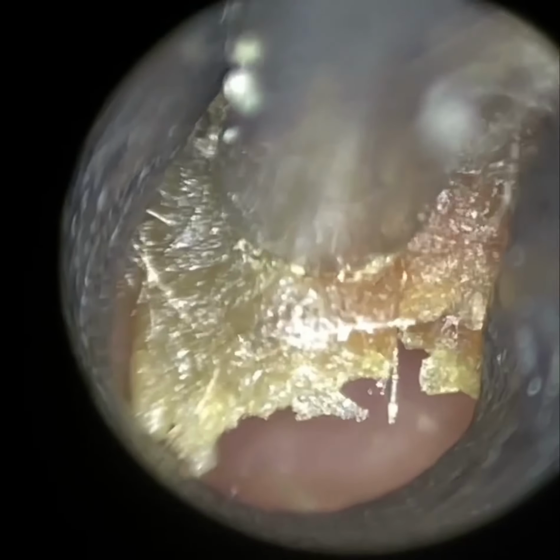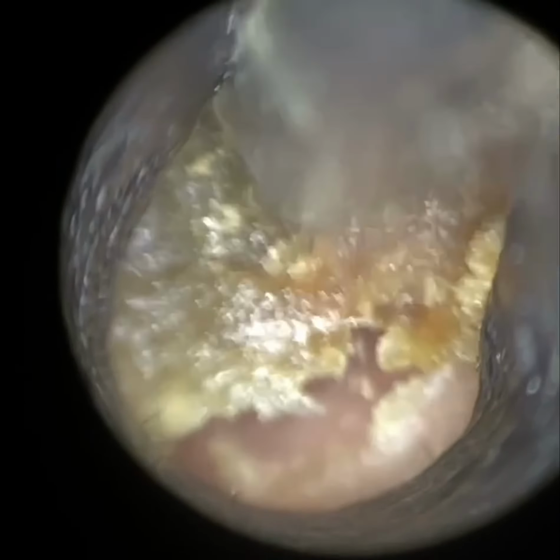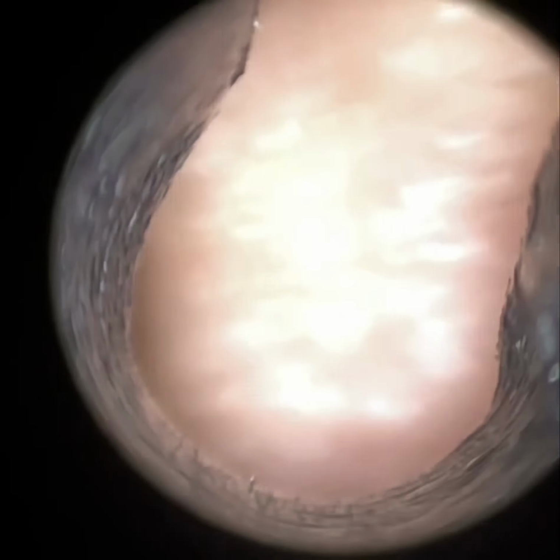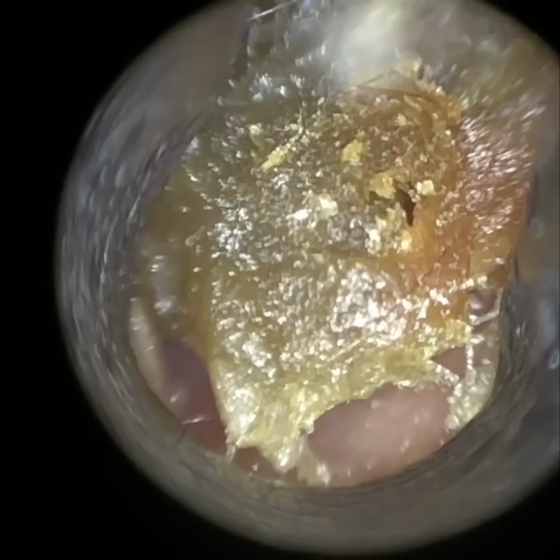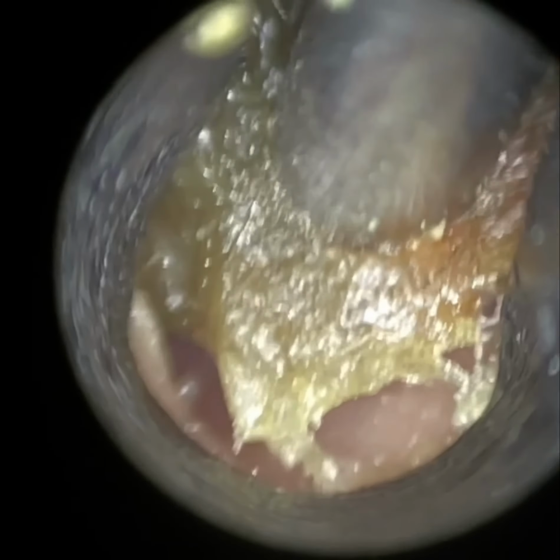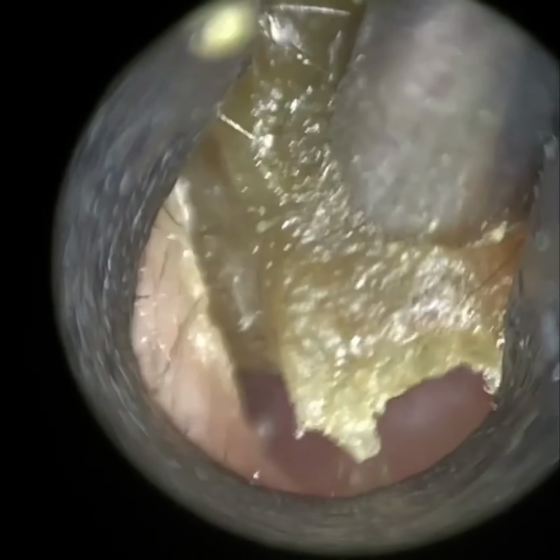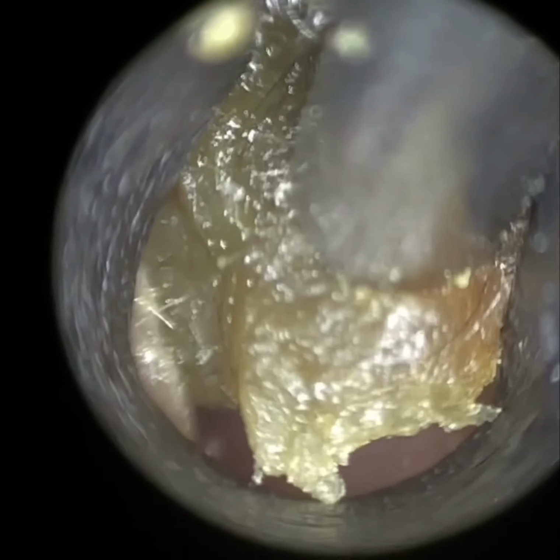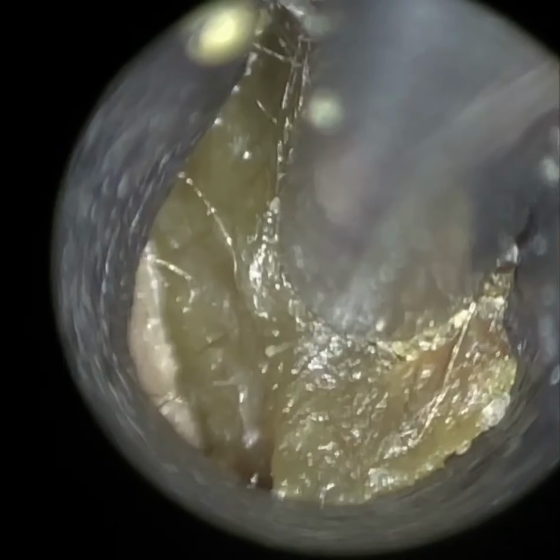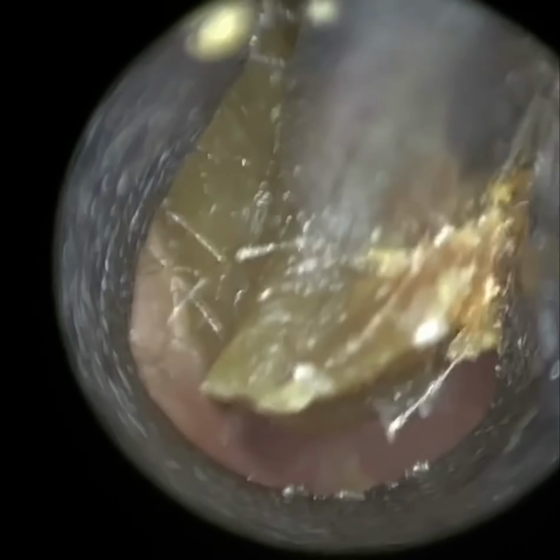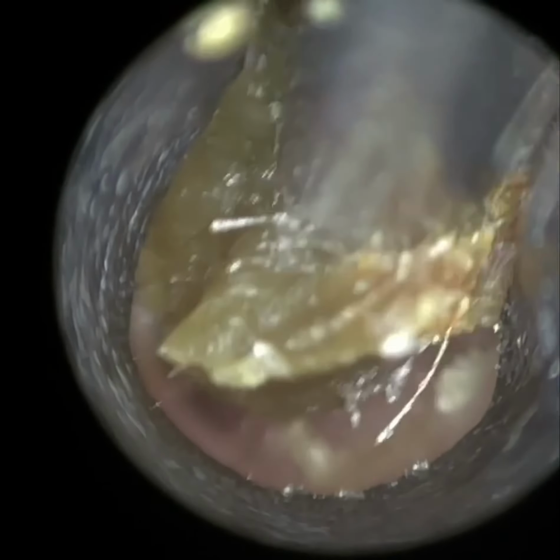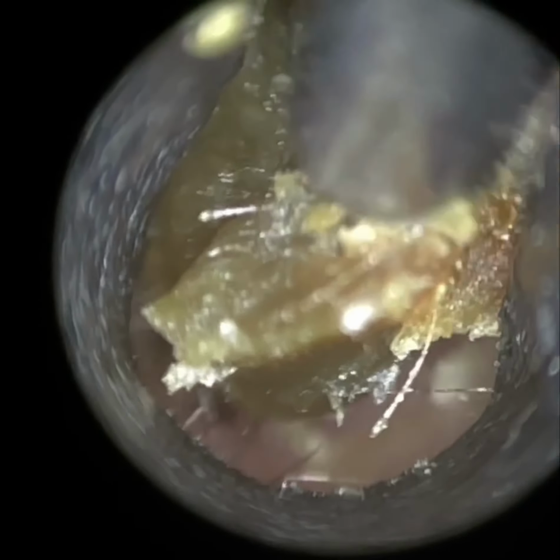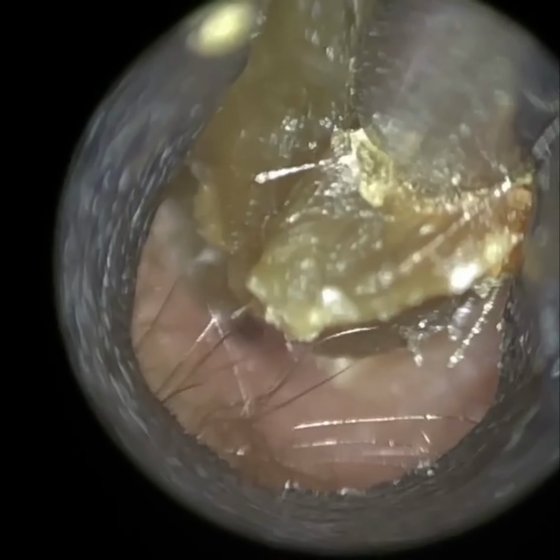this device is actually a class 1 medical device. It doesn't need a class 2 certification. Class 2 certification is when, in the case of an endoscope, there's a lumen, a cavity where you have to insert an instrument through, and that lumen is not disposable and is being reused. There has to be proper sterilization methods being used to do that. So with the WAXscope, we mitigate that because of the disposable speculum.